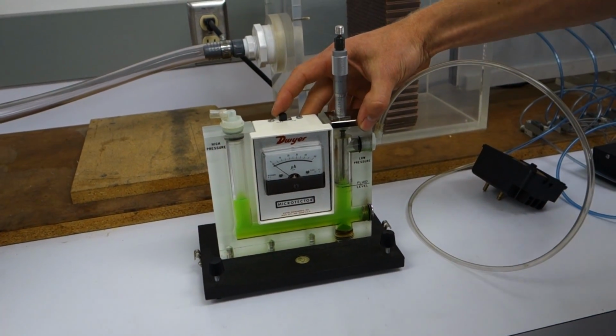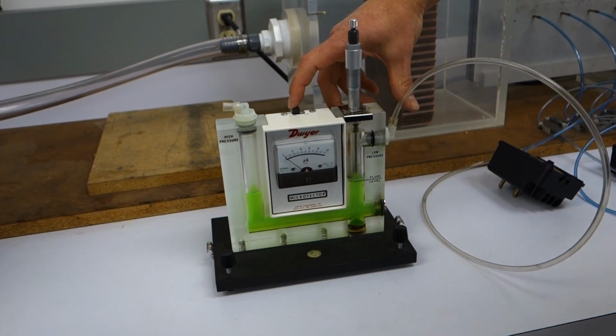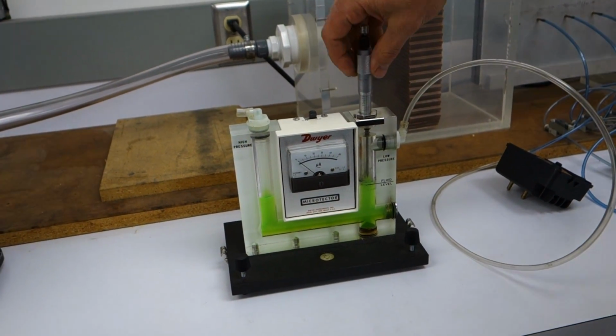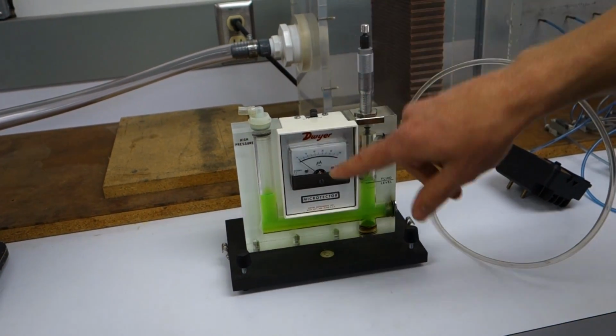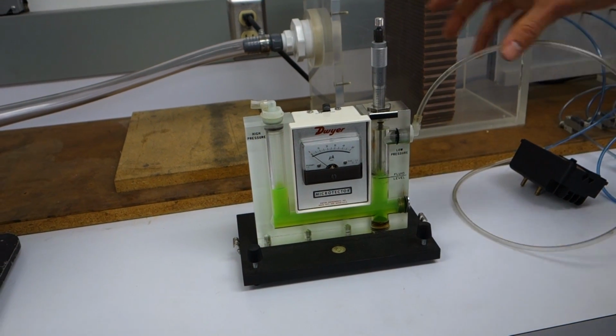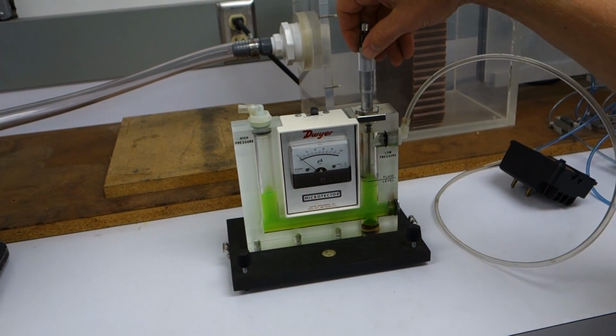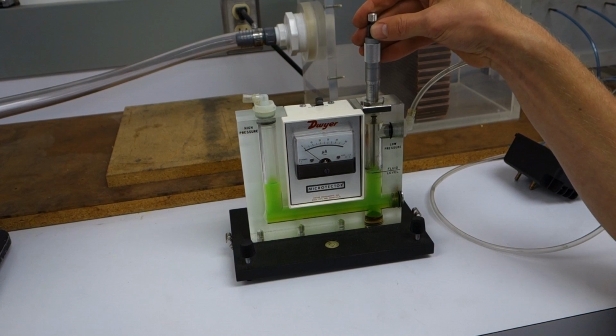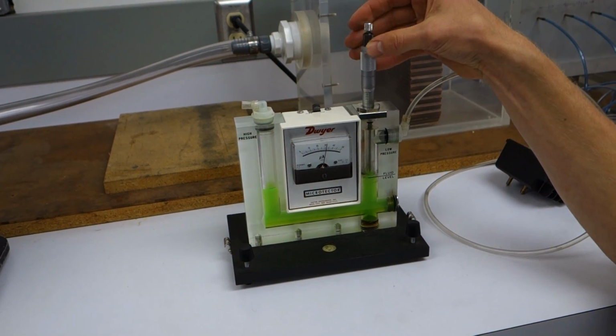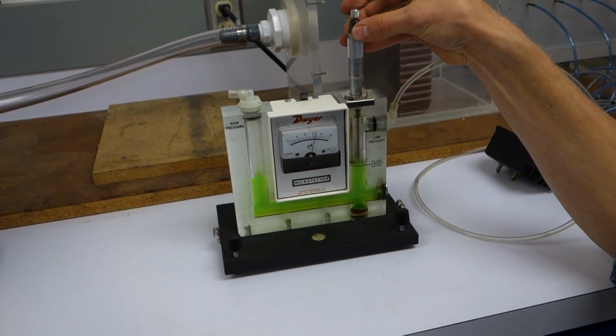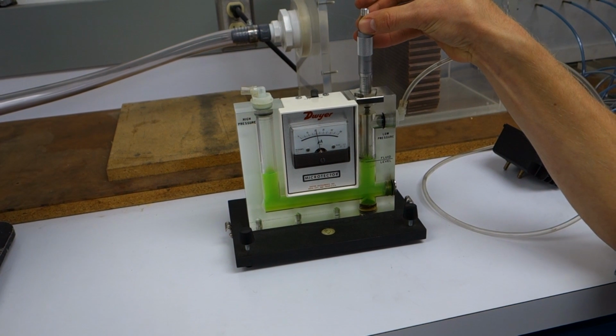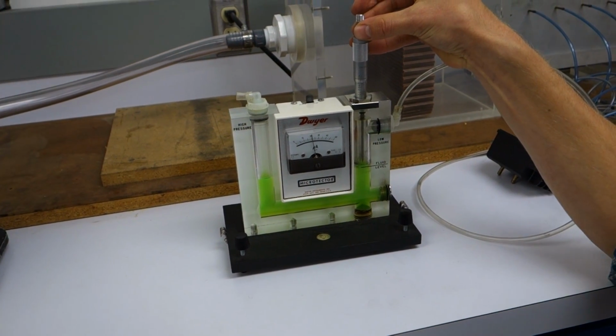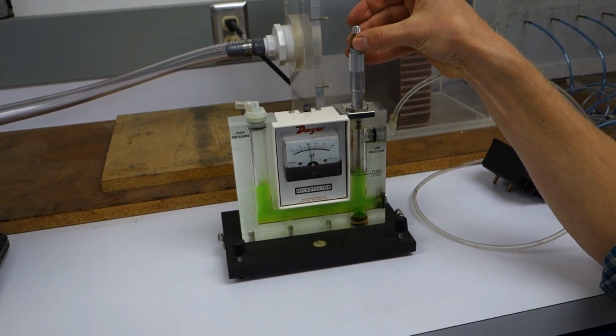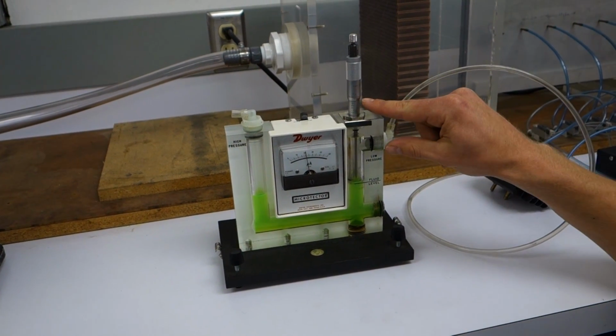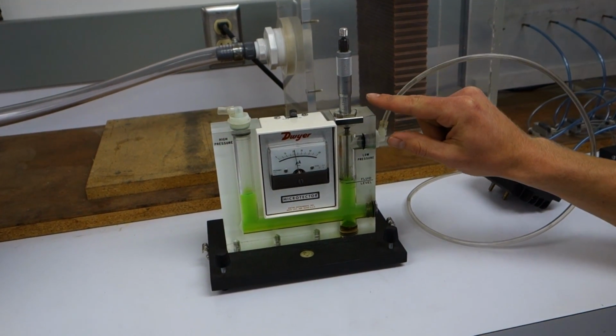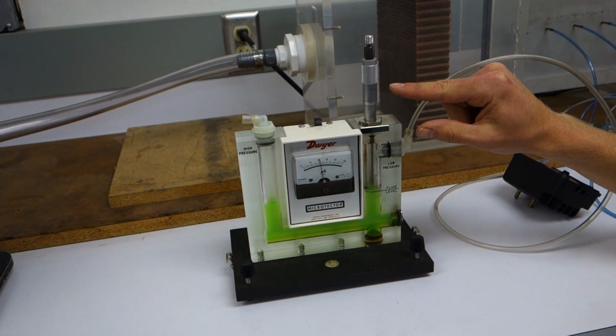So the way this works is as follows. Right now it's in the off position. We'll turn it on. And the probe is not submerged, so there's no current flowing. This is reading in microamps. What we'll do here is find a reference current. We're going to say 20 microamps is our reference current. And we'll submerge the probe just enough so that 20 microamps are flowing. Okay, 20 microamps. And we'll notice that this is a micrometer, which has accurate height measurements here.